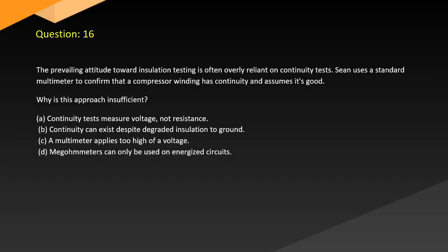Question 16. The prevailing attitude toward insulation testing is often overly reliant on continuity tests. Sean uses a standard multimeter to confirm that a compressor winding has continuity and assumes it's good. Why is this approach insufficient? A. Continuity tests measure voltage, not resistance. B. Continuity can exist despite degraded insulation to ground. C. A multimeter applies too high of a voltage. D. Megohmmeters can only be used on energized circuits.